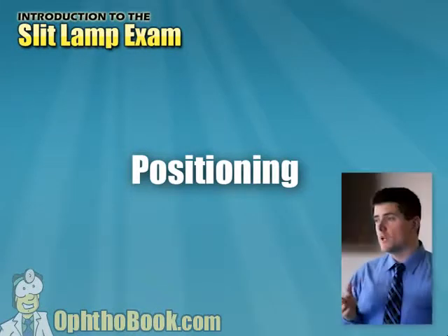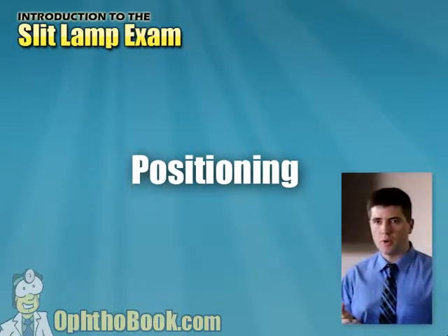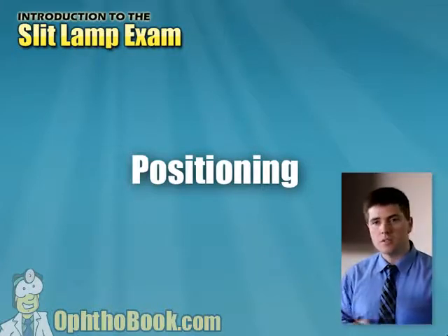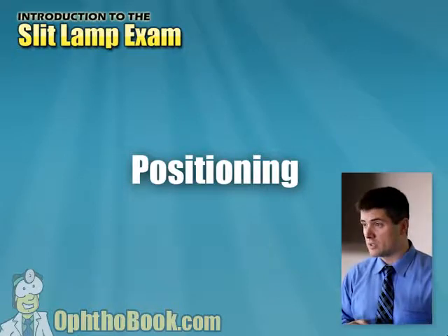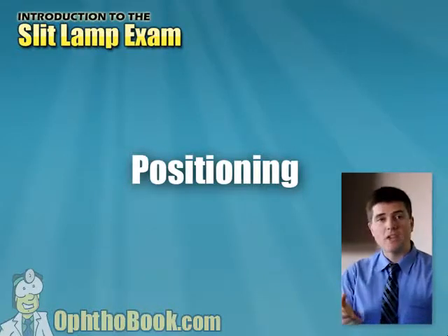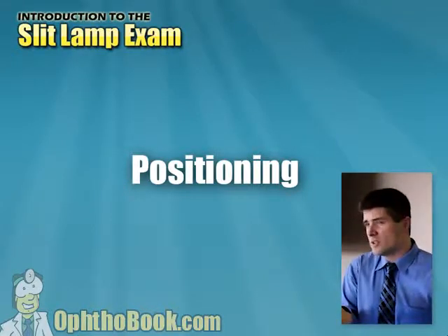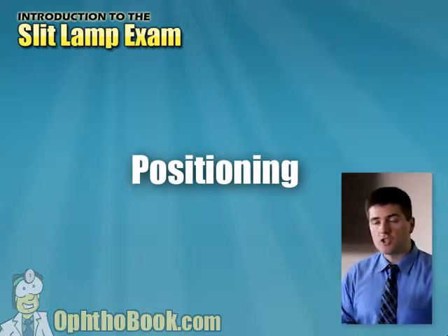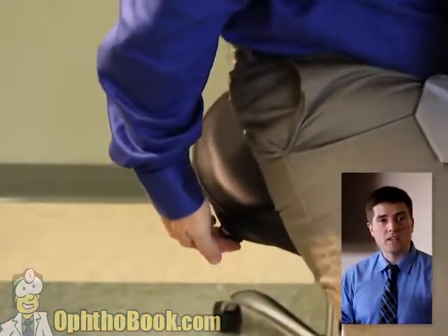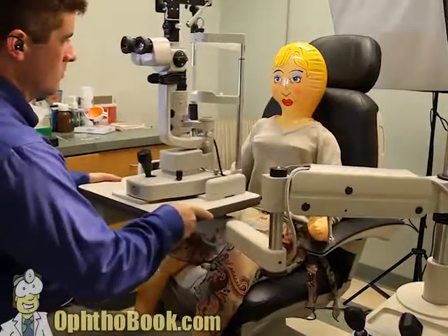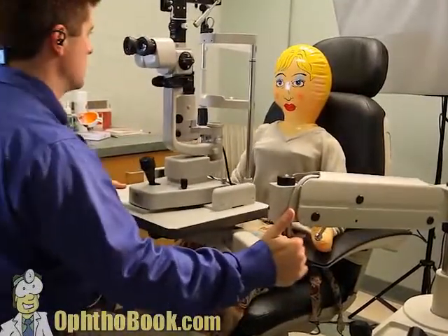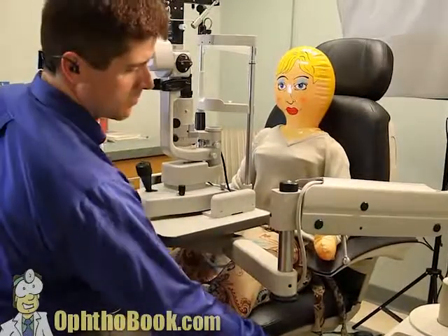Positioning. We've been trained from a customer service standpoint to always put your patient first, but when it comes to the slit lamp exam your comfort is actually more important. A patient is seen once or twice a year — you're doing this three or four thousand times a year. Talk about repetitive stress injury. So when you start with positioning, make yourself comfortable before you make your patient comfortable. That means setting the seat where you want to sit, then setting the microscope at the height that you like — there's usually a locking mechanism to the side.